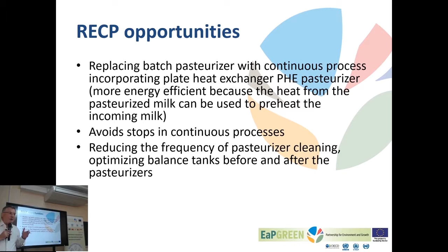If possible, especially in bigger installations, this will definitely be the more economical approach: pasteurization should be done as a continuous process in a plate type heat exchanger, with three sections — one for heating, one for heat recovery, which should be properly sized, and one for cooling. And again, our old topic which we've discussed a few times today: the pasteurizer should be operated continuously, if possible with no stops during the day and no need for additional cleaning during the day. This is a challenge for production planning, to use the equipment as continuously as possible.